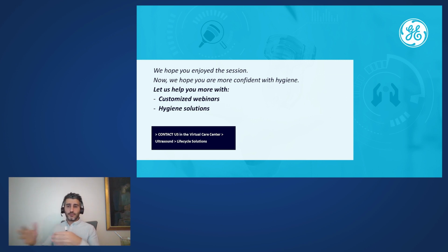So we were in contact with different departments around Sweden, around the Nordics, and we listened to our customers. We asked them questions. What do they need? How are they performing the disinfection and the cleaning of their probes? And then we build up a webinar together with the customer, and we go live to everyone who is working at that specific department. And then we went through step by step how you clean your probes, where you should focus on.